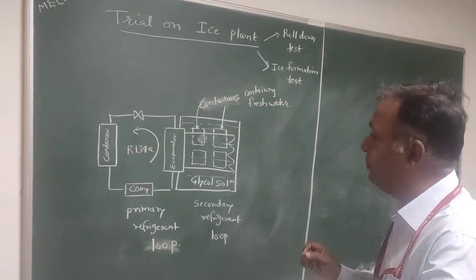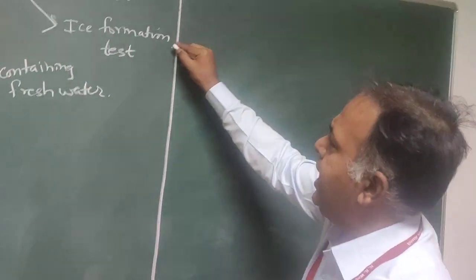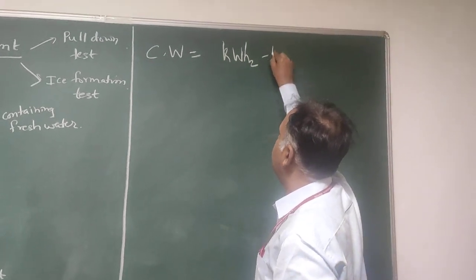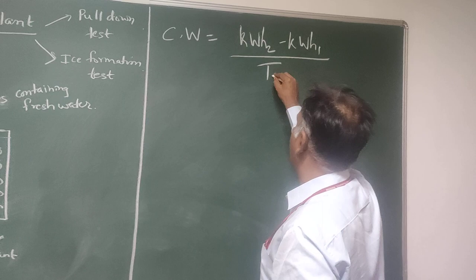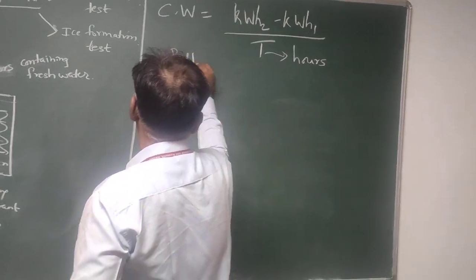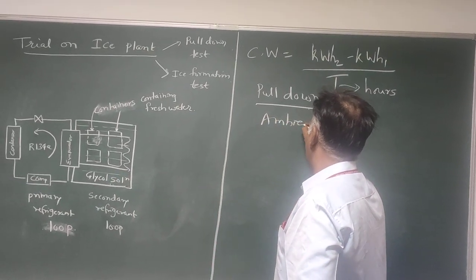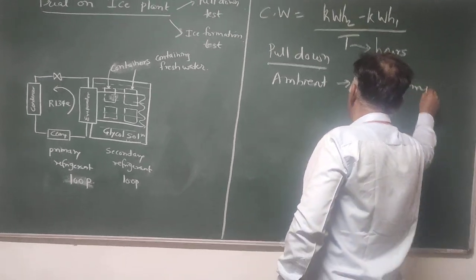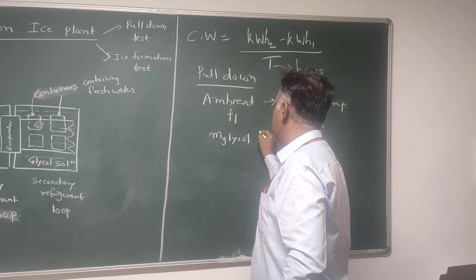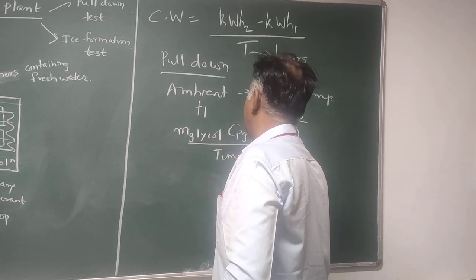For the pull down test calculations: in both tests — pull down test and ice formation test — the compressor work is calculated from the energy meter readings: final reading minus initial reading, with time converted to hours. For the pull down test, you pull down the temperature of the glycol from ambient to negative temperatures. Let T1 be the initial temperature and T2 the final temperature. Knowing the mass of glycol, specific heat of glycol, and ΔT divided by time gives you the refrigerating effect for the pull down test.